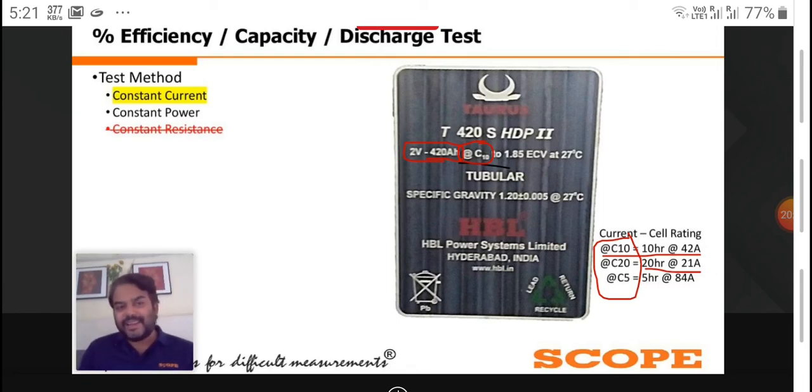While selecting the battery loading unit, you need to see parameters like the total battery bank voltage or string voltage, the total number of cells or individual cell voltage, and the type of battery. From that you get the voltage, because every battery loading unit comes with some pre-settings.